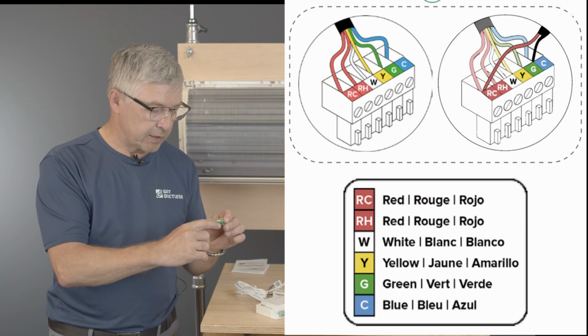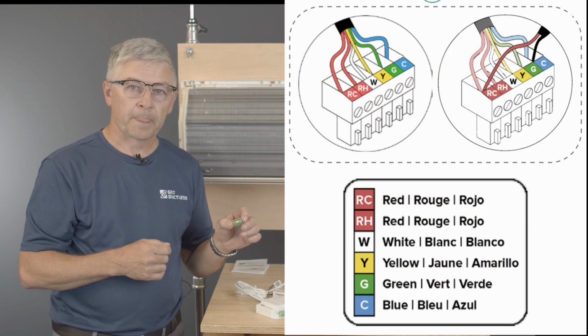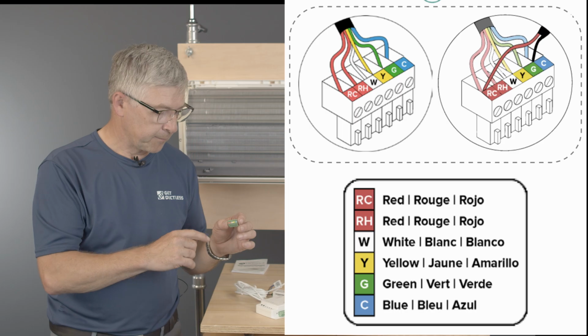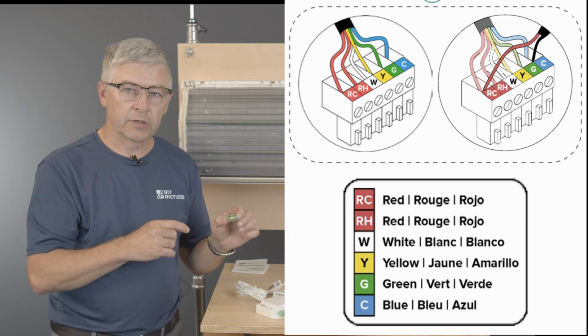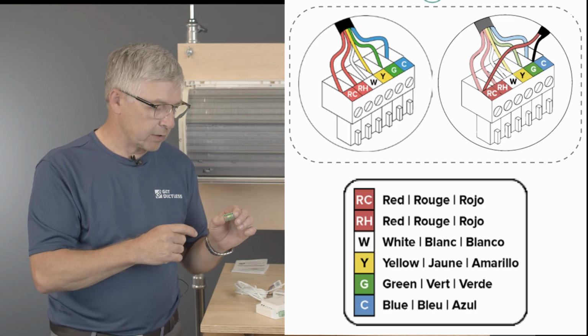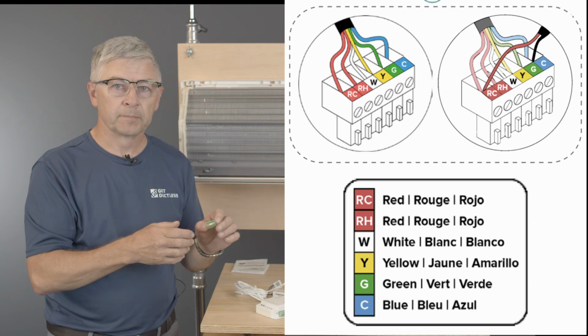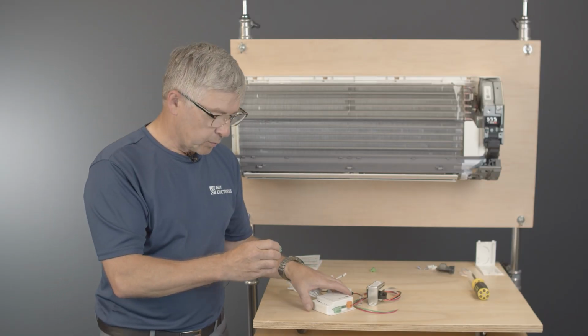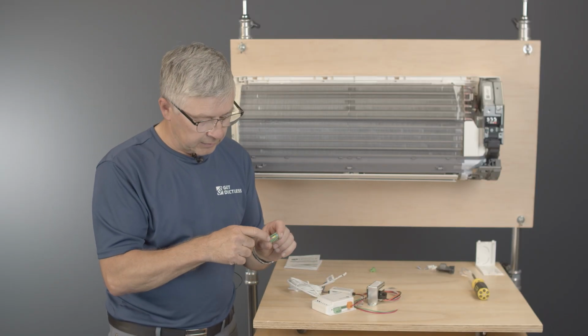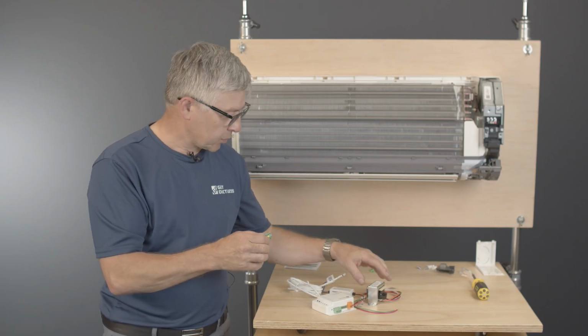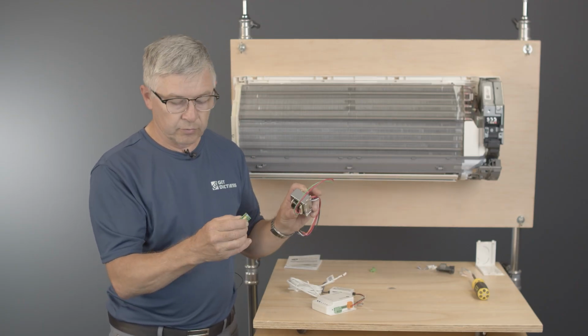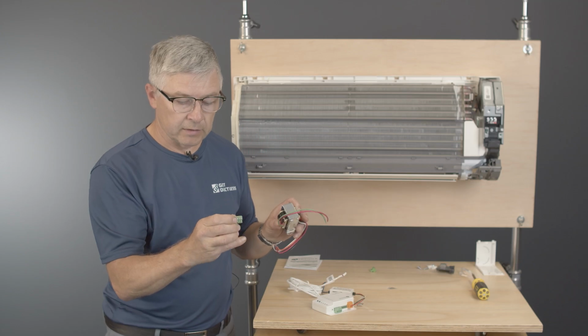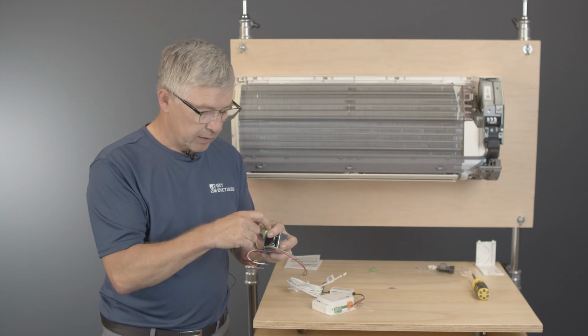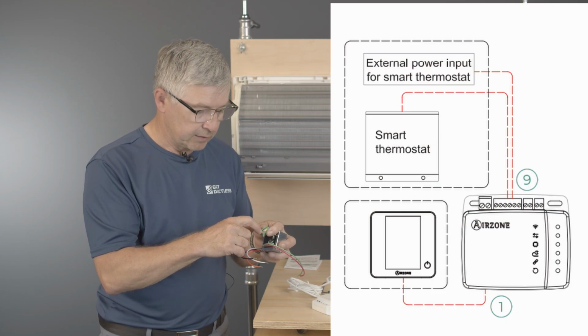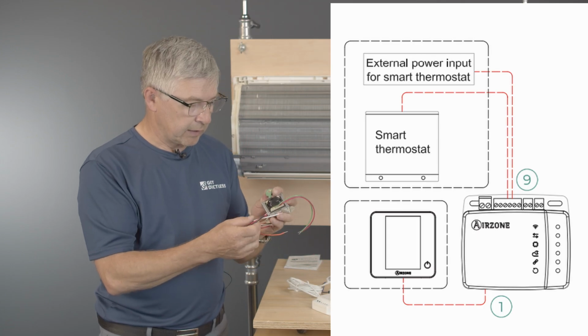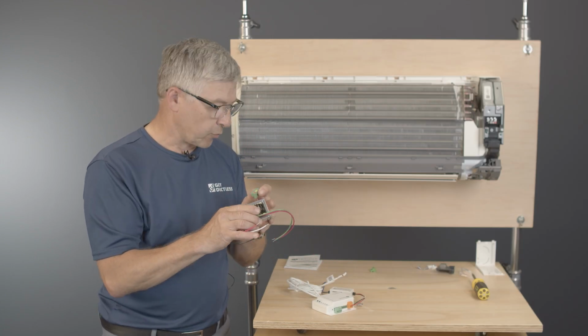So RC, RH, and common are your 24-volt power to the thermostat. The W is responsible for heating, Y is responsible for cooling, and G is responsible for the blower function. Once you've connected your thermostat to these specific wires, you also need to connect your transformer to the same connector, and you will be using common, or C, and RC with RH to connect your 24-volt transformer.